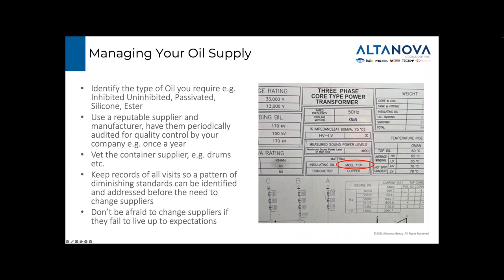Manufacturers are getting better at including this sort of information on the rating plate, but you may not always find the oil type on here. You might have to refer to other documentation or even take a sample to identify the oil type in your transformer. You'll also notice the cooling to the left of the Midel is K-NAN rather than O-NAN.